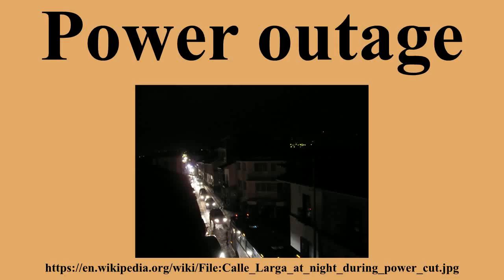Protecting the power system from outages. In power supply networks, the power generation and the electrical load must be very close to equal every second to avoid overloading of network components, which can severely damage them. Protective relays and fuses are used to automatically detect overloads and to disconnect circuits at risk of damage. Under certain conditions, a network component shutting down can cause current fluctuations in neighboring segments of the network, leading to a cascading failure of a larger section of the network. This may range from a building, to a block, to an entire city, to an entire electrical grid.